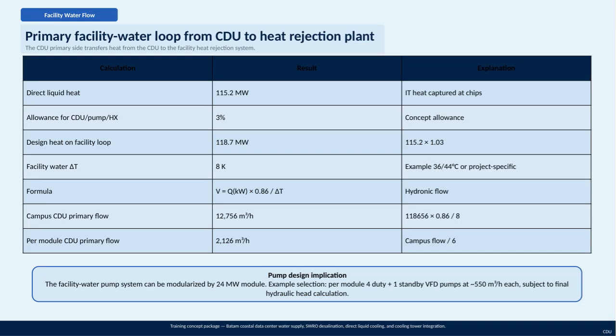Here we're focusing on the facility water flow, specifically the primary water loop that connects the CDU or cooling distribution unit to the heat rejection plant. The primary side of the CDU plays a crucial role by transferring heat from the CDU to the facility's heat rejection system, helping manage the thermal load effectively. This training concept package covers several integrated systems, including the Batam Coastal Data Center water supply, seawater reverse osmosis desalination, direct liquid cooling, and the cooling tower integration, all working together to optimize cooling efficiency.